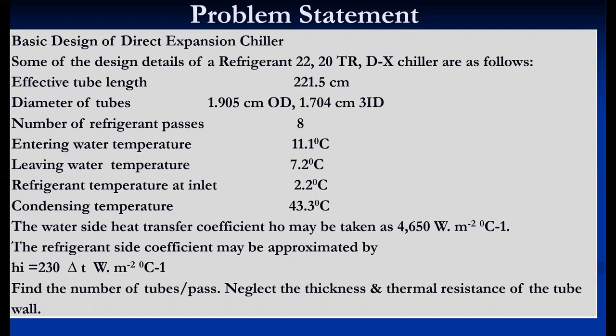The entering water temperature is 11.1°C, leaving water temperature is 7.2°C, refrigerant temperature at inlet is 2.2°C — which is the evaporating temperature. Since the refrigerant temperature at the outlet is not given, we assume the state is saturated at the outlet. Condensing temperature is 43.3°C. Water side heat transfer coefficient H_o and inside coefficient H_i are given. We need to find the number of tubes per pass, assuming tube wall thermal resistance is negligible.